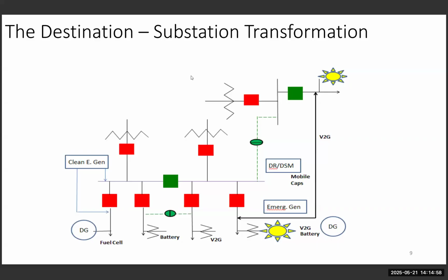So again, we started with just two transformers, four circuits. Now we have the same thing, but we're showing another substation. It's very common for a supply feeder to supply multiple stations. We don't have an unlimited amount of circuits, so when you lose that circuit, you lose multiple substation transformers.